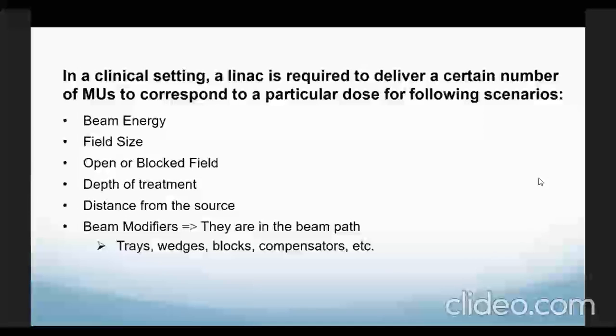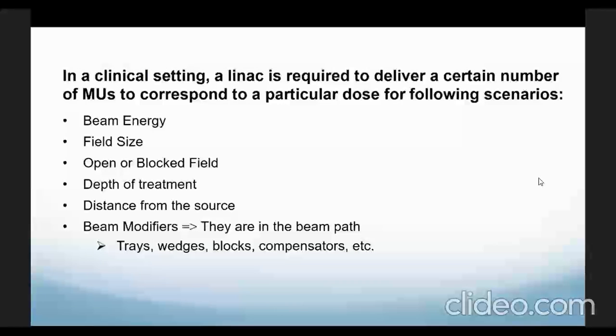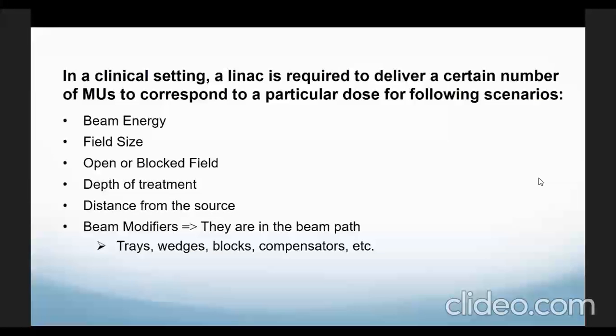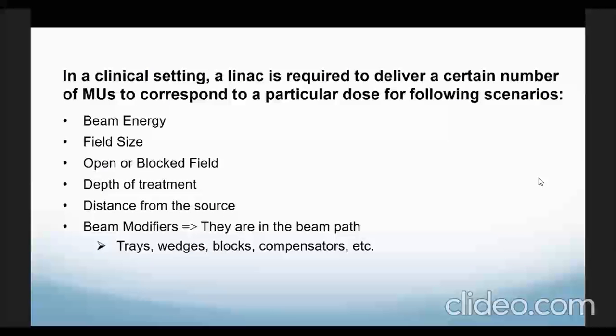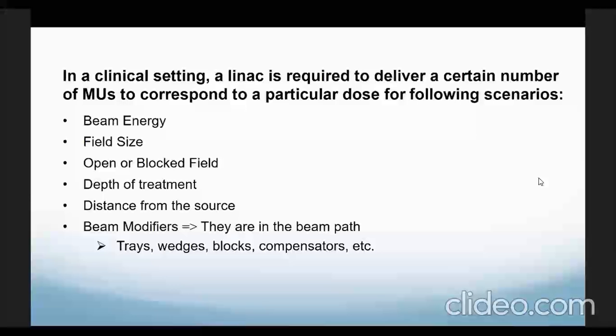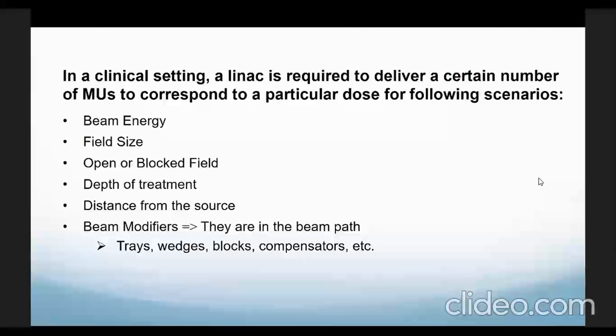In a clinical setting, a linear accelerator is required to deliver a certain number of MUs to correspond to a particular dose for one or more of the following scenarios: beam energy, field size, whether the field is open or blocked, and depth of the treatment in the patient.